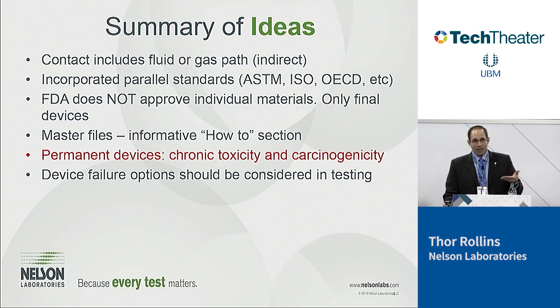So we know the materials for the most part are safe. And the ones that aren't necessarily safe or have some problems, like for example, silver or latex, things like that, we know what the risk is. So the materials themselves aren't necessarily the issue. What we've seen as the issue is the residuals from the processing. If you're going to fail a test unexpectedly, most of the time that unexpected failure comes from something that's done in the process of that device.